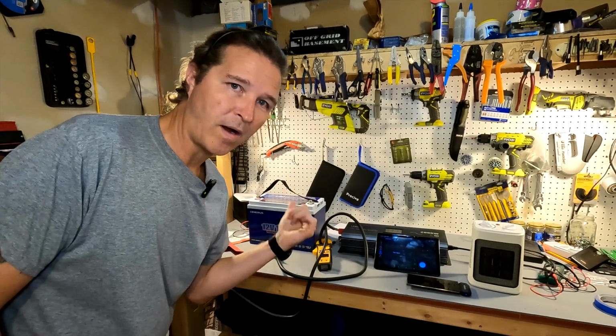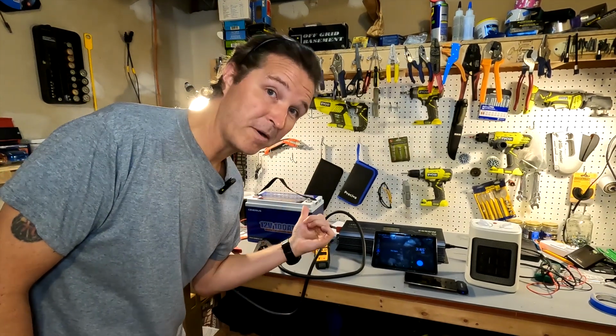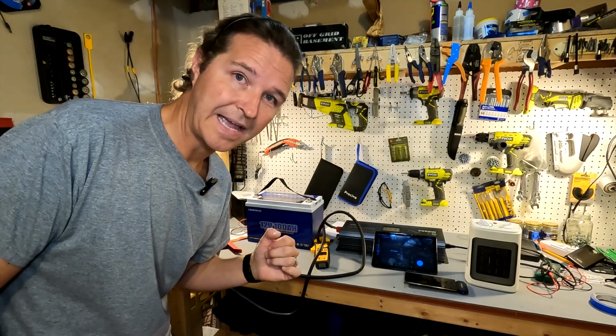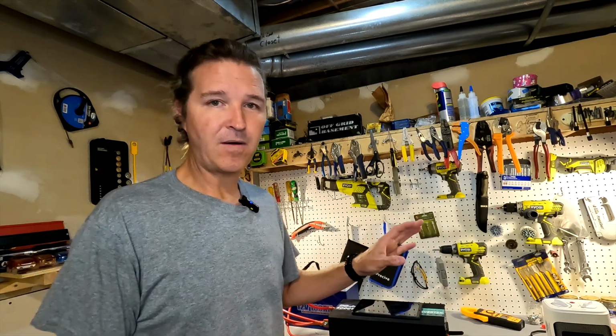So I'm going to go ahead and wire this up with a proper set of wiring, and we're going to run this test again. It did make it 3 minutes and 45 seconds at 160 amps, which is, I don't know if that's concerning or great. I feel like the battery should shut off before that, but I was really worried because those terminals were getting way over 300 degrees. So I went ahead and bumped up pretty much all my connections.